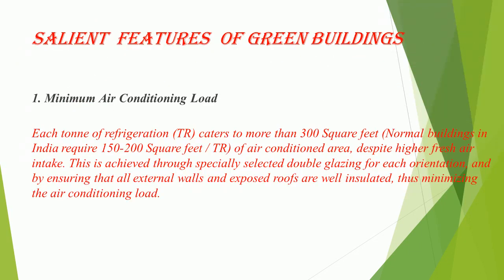Salient Features of Green Buildings. Feature 1: Minimum air conditioning load — each ton of refrigeration (TR) caters to more than 300 square feet, whereas normal buildings in India require 150 to 200 sq. ft. per TR of air-conditioned area, despite higher fresh air intake. This is achieved through specially selected double glazing for each orientation and by ensuring all external walls and exposed roofs are well insulated, thus minimizing the air conditioning load.